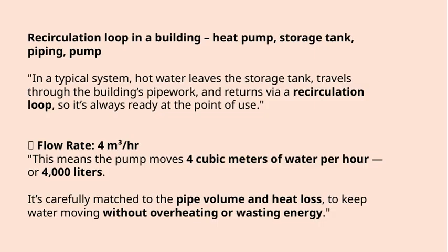This setup ensures that hot water is always readily available right at the point of use, reducing wait times and improving efficiency. The flow rate in this system is about 4 cubic meters per hour. To put that into perspective, that's roughly 4,000 liters of water moving through the system each hour.